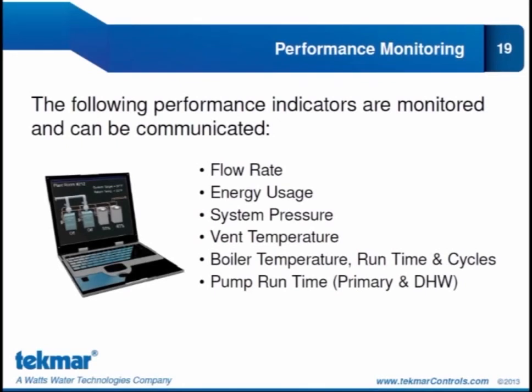Now, what information can be communicated to a building automation system? Well, in addition to temperatures, system performance monitoring information can also be communicated. The first of those indicators that can be measured and communicated is flow rate. If we are connected to a flow sensor, and the flow sensor, as I mentioned before, is a 0 to 10 volt analog vortex style flow sensor. If we have that, and we also have the boiler supply sensor and the boiler return sensor, then we can calculate the energy usage and we can communicate that to the BAS as well.